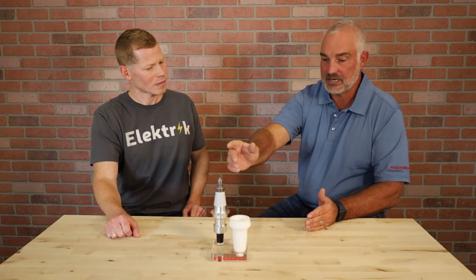The biggest thing, if you're comparing similar sizes: a 600 amp t-body, by its name, is good for up to 600 amps — unless you give it an all-copper current path, and then it's good for 900 amps. But that's its limitation. As cables are getting larger and larger, t-bodies are going to be stuck at that 600 to 900 amp rating. This other product gets a 1250 amp rating. That's the difference — that's a game changer.